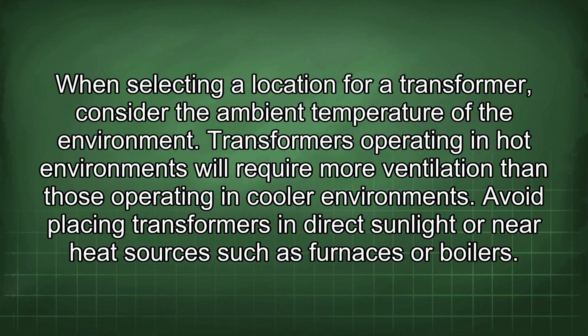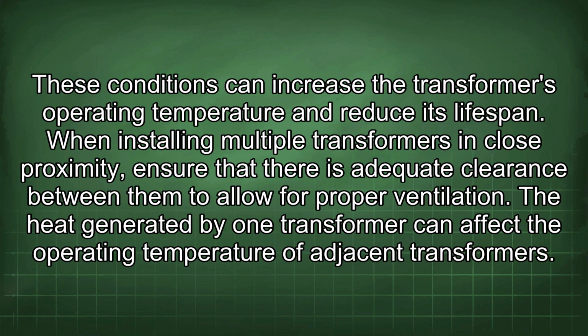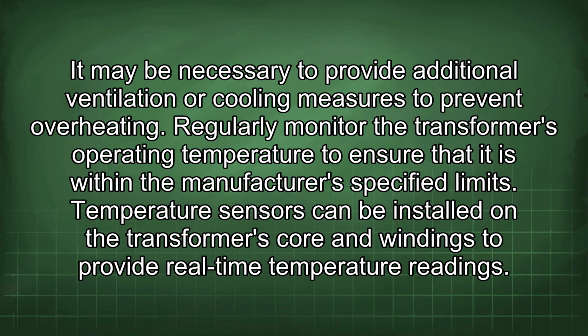When selecting a location for a transformer, consider the ambient temperature of the environment. Transformers operating in hot environments will require more ventilation than those operating in cooler environments. Avoid placing transformers in direct sunlight or near heat sources such as furnaces or boilers. These conditions can increase the transformer's operating temperature and reduce its lifespan. When installing multiple transformers in close proximity, ensure that there is adequate clearance between them to allow for proper ventilation. The heat generated by one transformer can affect the operating temperature of adjacent transformers. It may be necessary to provide additional ventilation or cooling measures to prevent overheating.